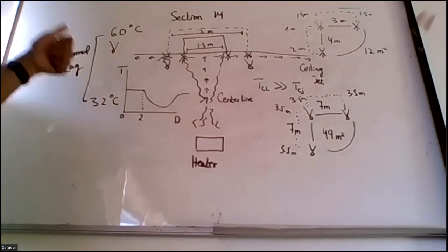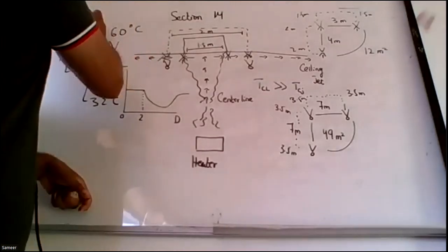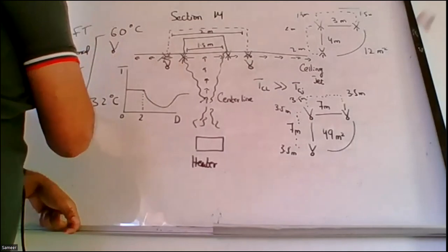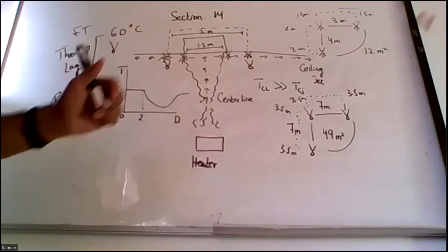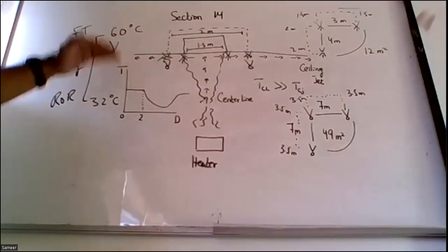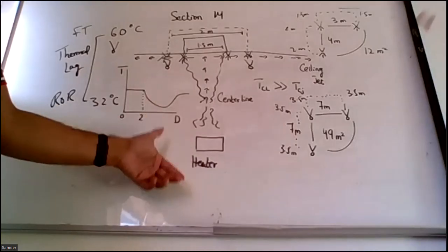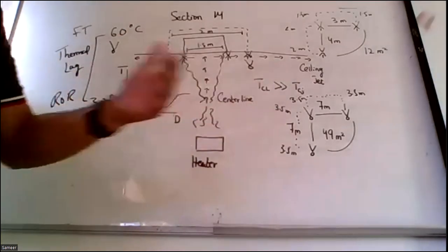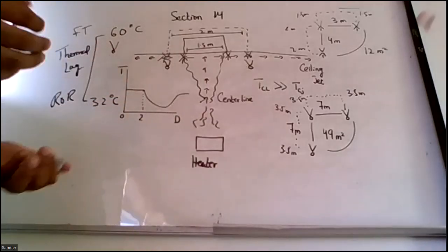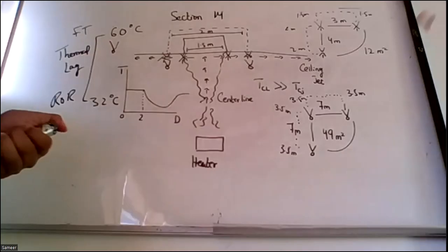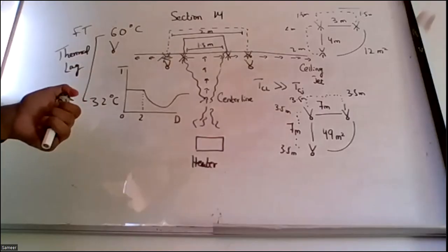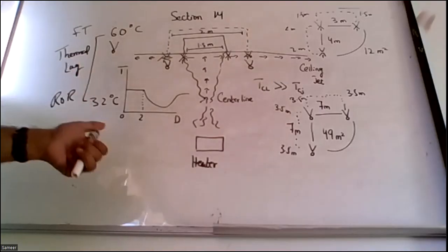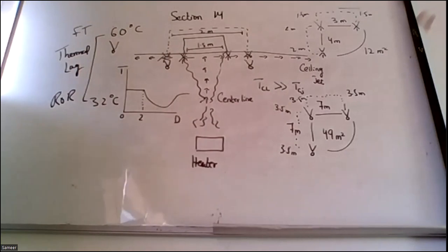Fixed temperature and rate of rise heat detectors have a very low thermal lag feature, meaning as soon as there is a temperature differential, these detectors will operate. This is a problem in areas where I already have heaters or commercial cooking appliances, like hotels and restaurants. When they have heat detectors nearby, the detectors trigger. They don't have any option, so they think the heat detectors are faulty, but actually heat is escaping and really reaching the fixed temperature threshold. To avoid that problem, we want a type of detector that does not detect heat only from one point.